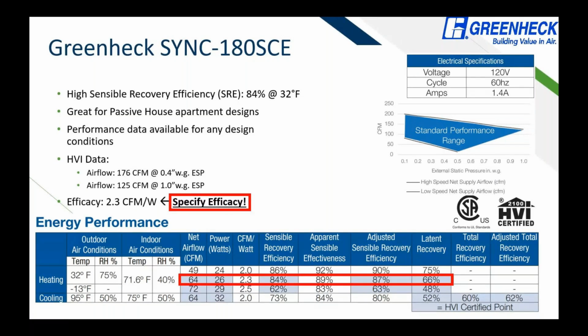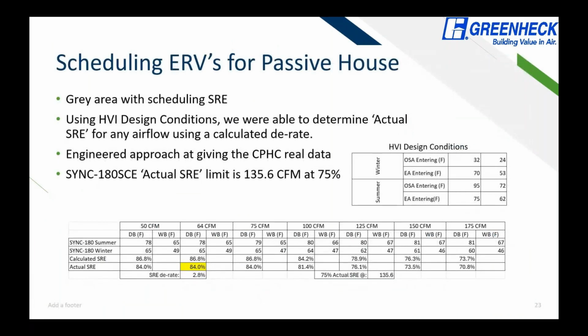You actually have a high airflow of 176 CFM at 0.4 inches static pressure, 125 CFM at 1 inch, which is usually plenty. And then down here, right here, I have highlighted an HVI data point. Now, this is going to get a little tricky, so please give me any feedback if you don't necessarily get what I'm getting at. But when you work with these CPHCs or the PHIUS people, if you're a CPHC yourself, maybe you understand this. They always like to reference these HVI data points, but they're constrained to the actual design conditions and airflows that they provide.